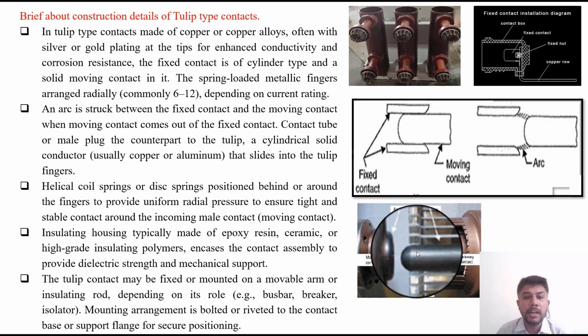The contact tube or male plug, the counterpart of these tulip type contacts, is a cylindrical solid conductor, usually copper or aluminum. This slides into the tulip fingers, like this. This is the male contact and this is how it is connected. A helical coil spring or disc springs are positioned behind or around the fingers to provide uniform radial pressure, to ensure tight and stable contact around the incoming male contact. This is a spring contact which holds tight this male contact or moving contact.